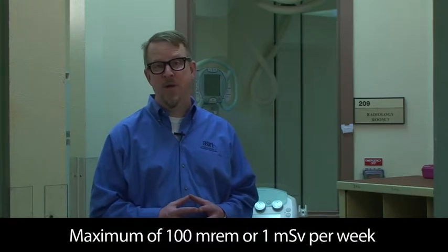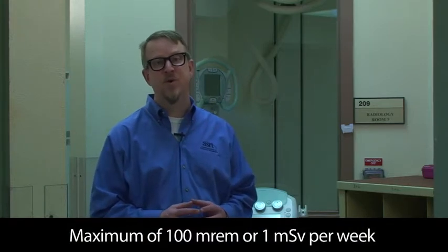Although the chosen imaging method may affect patient dose, the same types of protection apply for radiologic technologists regardless of the imaging method. The control booth is a safe area behind secondary barriers. If the construction of the room is up to code, the radiation in this area will be held to a maximum of 100 millirem or 1 millisievert per week.